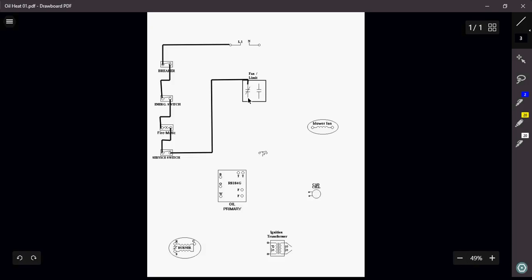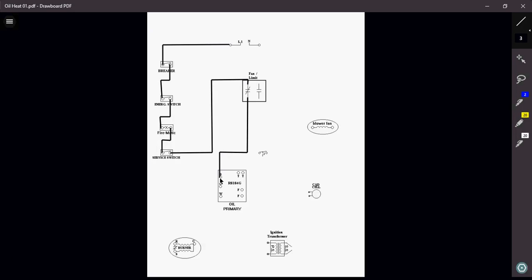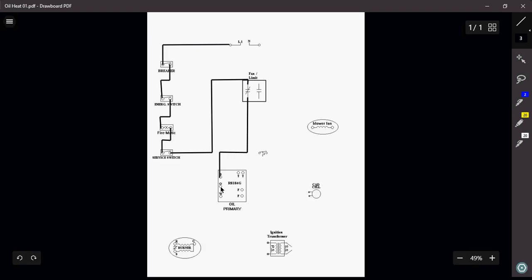Now, I'm going to come out of this side of our switch, and I want to bring it down to actually my primary control, which is an R8184G. It's one of the simplest of our primary controls that are out on the market. It's an old-style three-wire primary control. So, B is for our black wire, which is our power wire. Now, I'm going to switch. You're going to see that we have a B, an O, and a W. This is a three-wire primary control. Our black wire is for our power. White is our neutral. O, which is going to be an orange wire, will actually be what's going to be sent out to control our burner and our ignition transformer.